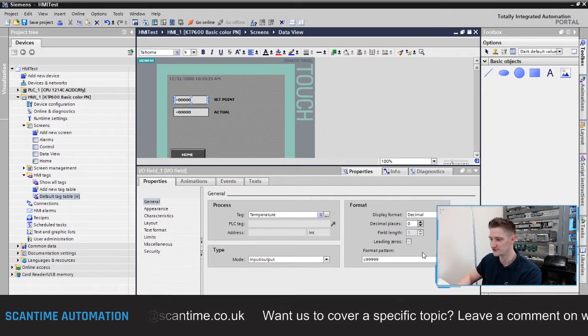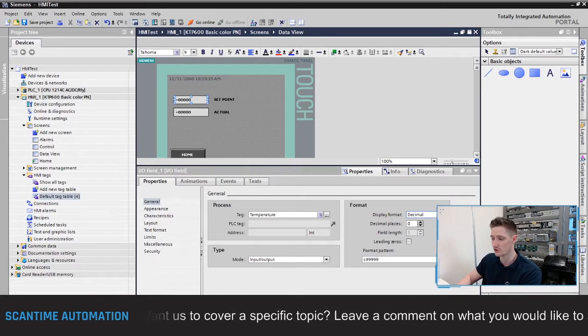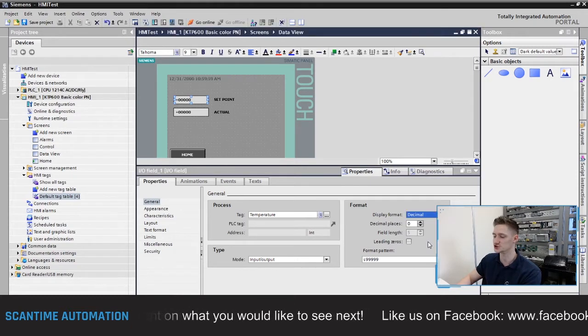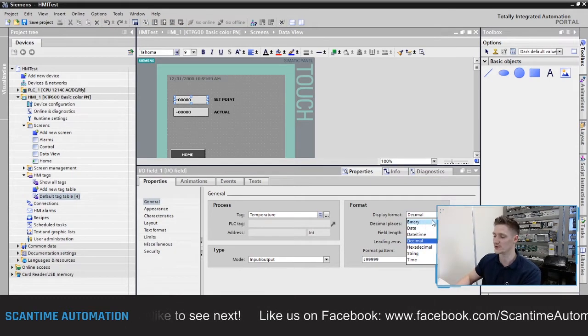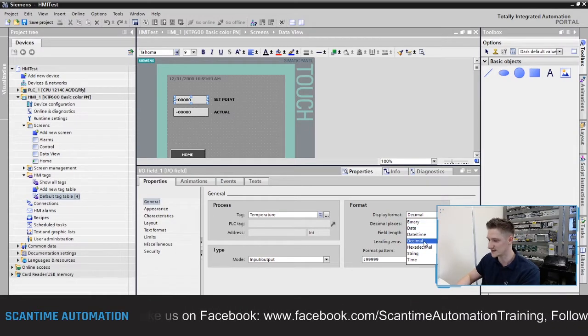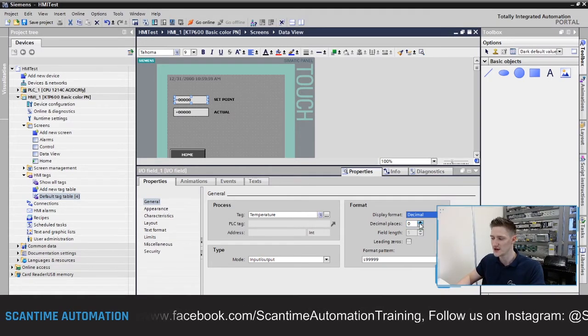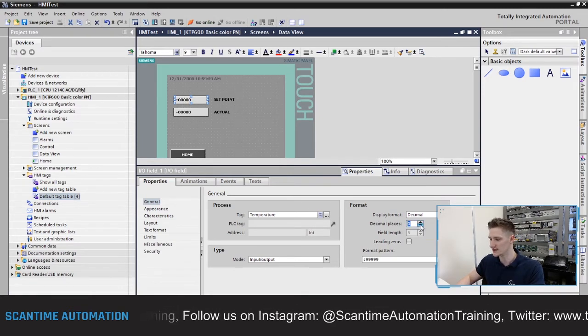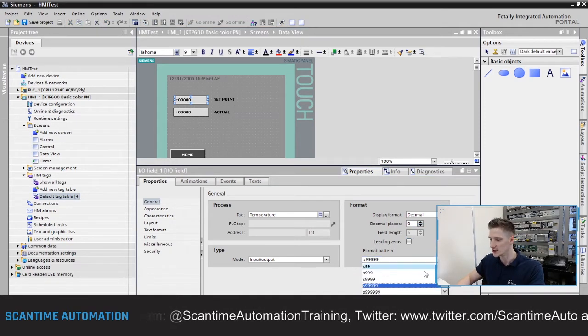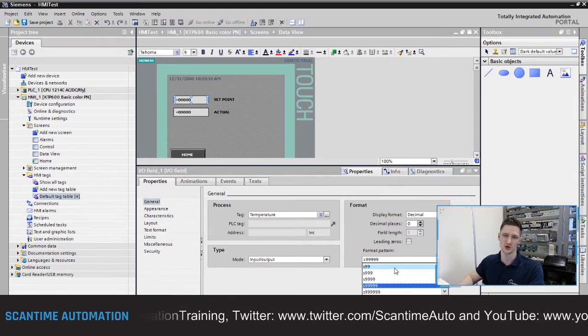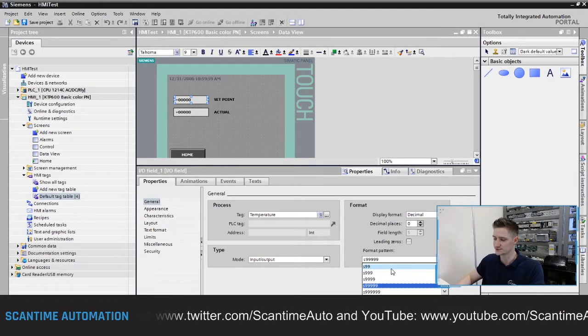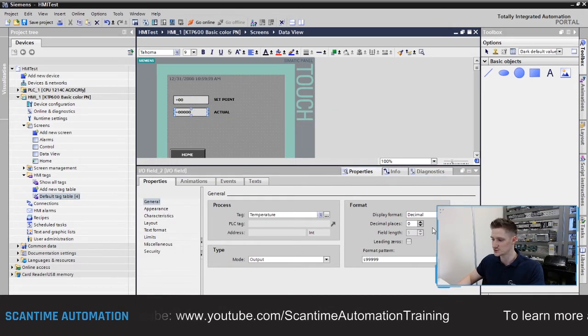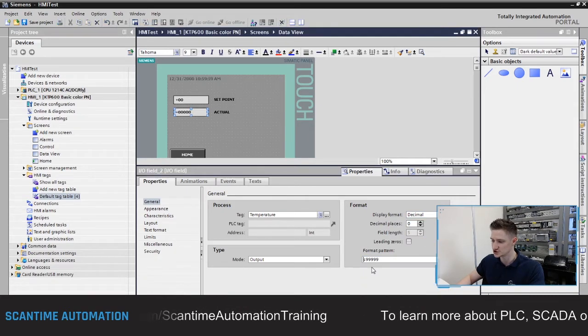In the Format section you can choose how to display the value — binary, date, date and time, decimal, hexadecimal, string, or time. I'm going to select decimal so it's easily read by the operator. Decimal places is currently set to zero; changing it to one would show a decimal place. I'll leave it as a whole number. For the format pattern I'll display it as two digits using 'S99', since my temperature will only go up to about 20 degrees on this HMI. I'll apply the same settings to the Actual IO field.